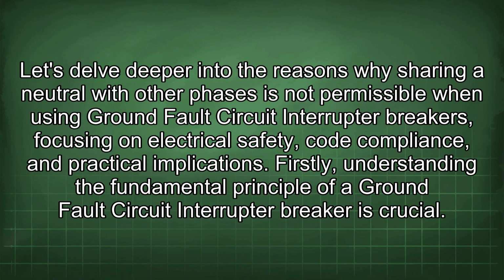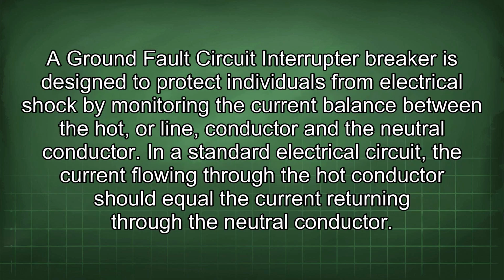Let's delve deeper into the reasons why sharing a neutral with other phases is not permissible when using ground fault circuit interrupter breakers, focusing on electrical safety, code compliance, and practical implications. Firstly, understanding the fundamental principle of a ground fault circuit interrupter breaker is crucial. A ground fault circuit interrupter breaker is designed to protect individuals from electrical shock by monitoring the current balance between the hot, or line, conductor and the neutral conductor.